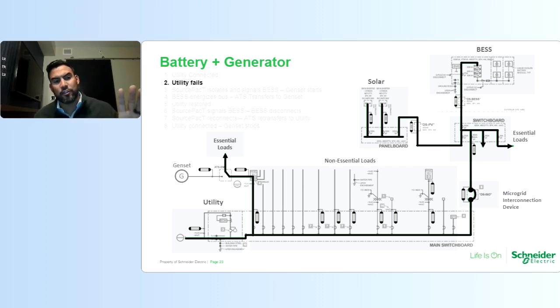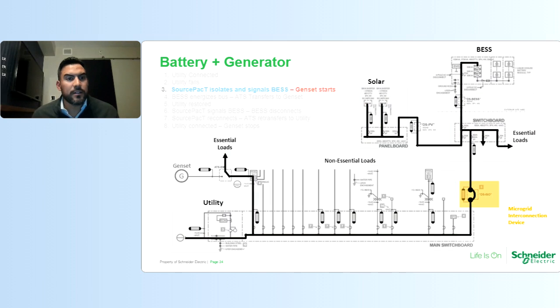Now here, because the ATS is already separate and is providing power to its own respective loads, and the microgrid interconnection device is providing power to its own respective loads, they both operate independently. So SourcePacT will detect through the controller that there's been a utility outage. It will open the electrically operated breaker. At the same time, the controller will signal to the inverter system of the battery energy storage system or energy management system supervising the entire microgrid that we're safely disconnected from the grid. At the same time, the ATS will signal the generator to come online. Again, the generator takes about 4 to 6 seconds to come online. The energy storage system with the inverters will come online almost instantaneously.